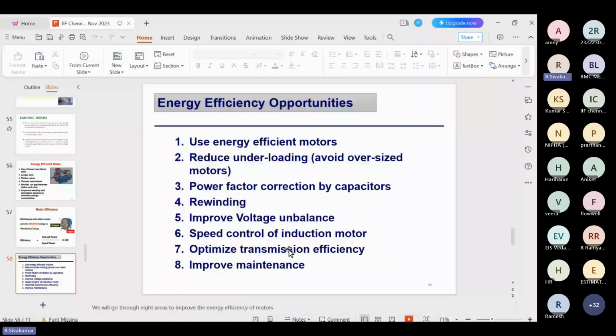So the energy efficiency opportunities in motors are: use energy efficient motors, reduce under-loading, and power factor correction by capacitor. For motors above about 10 HP, you may consider the load and compensation capacitance, so that the capacitor is added in parallel with the motor. The moment the contactor is on, the power factor capacitor is added, so that your power factor is corrected in the field itself.